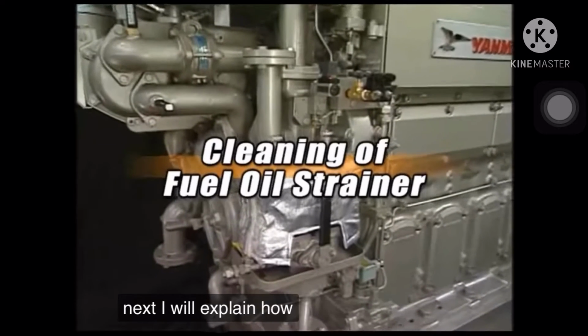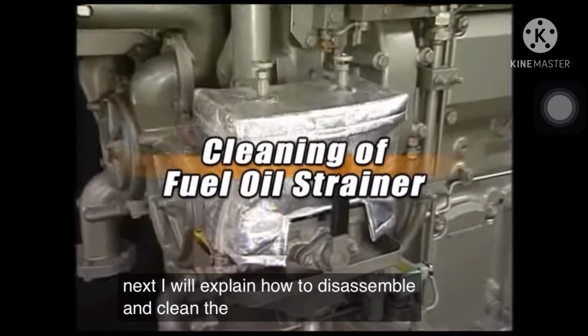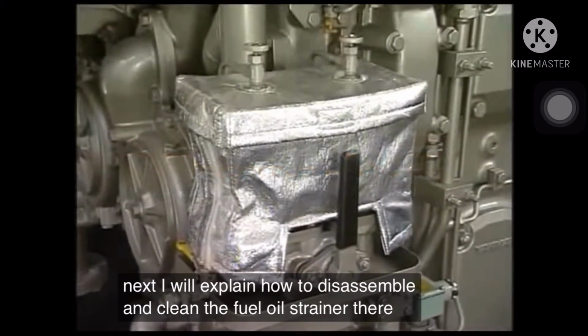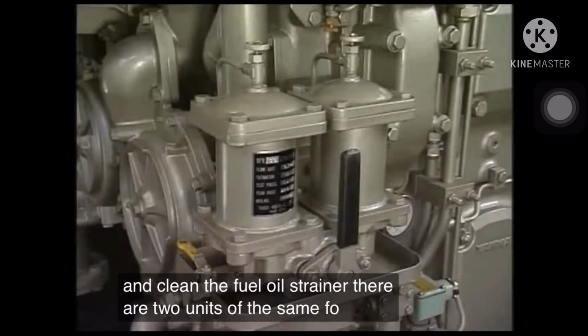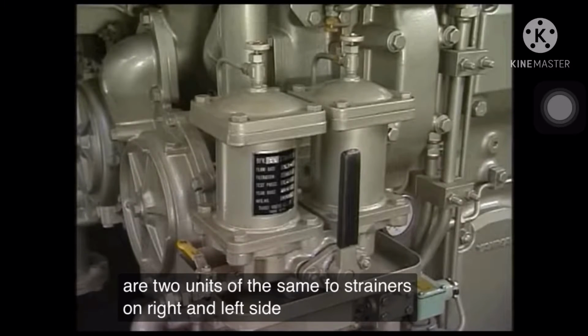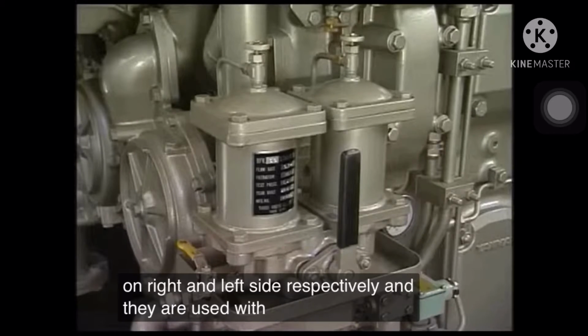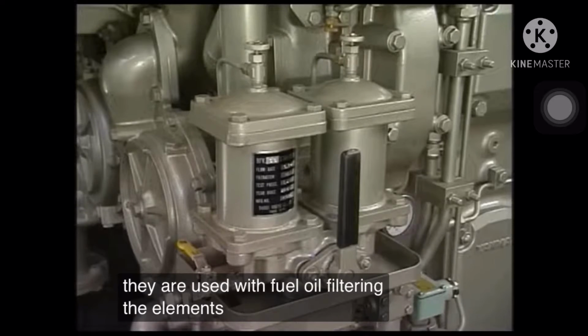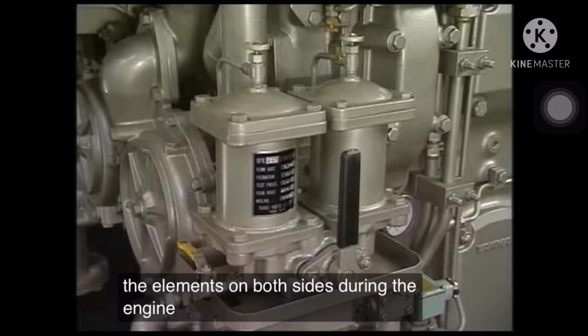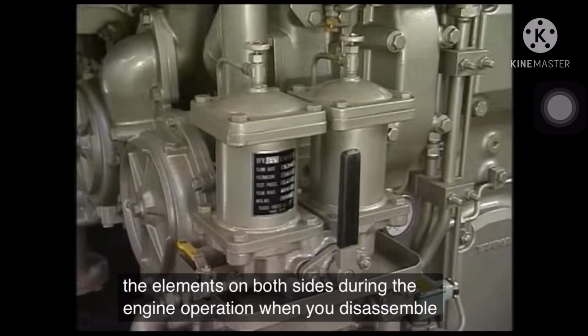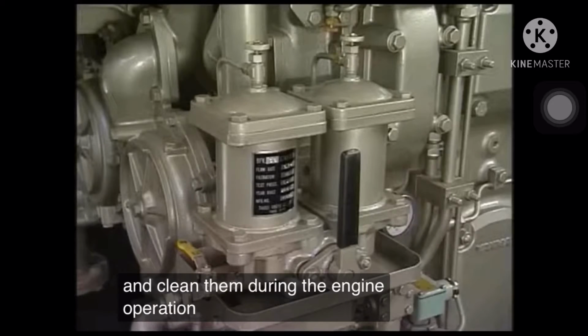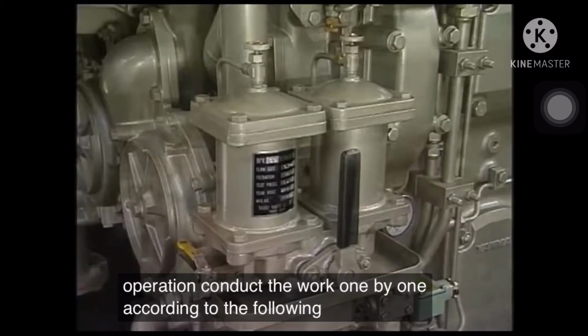Next, I will explain how to disassemble and clean the fuel oil strainer. There are two units of the same FO strainers on the right and left side respectively, and they are used with fuel oil filtering the elements on both sides during the engine operation. When you disassemble and clean them during the engine operation, conduct the work one by one according to the following procedure.